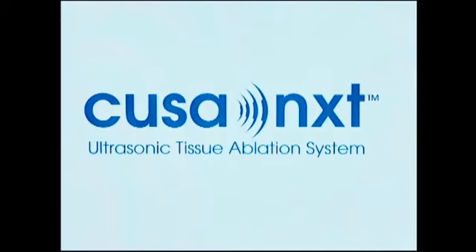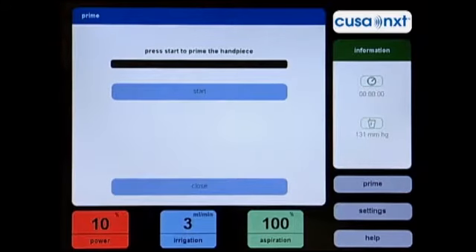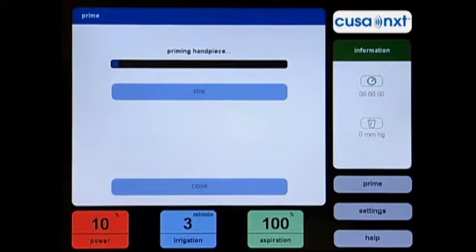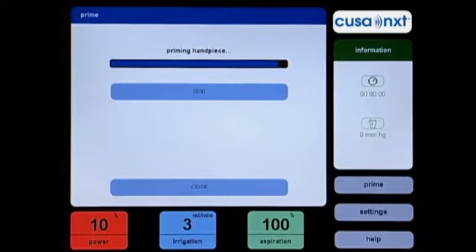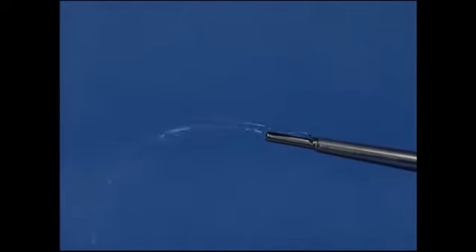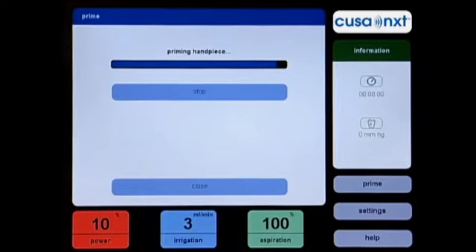After the system computer has successfully booted up, you will see the Prime screen. Press the Start button to automatically prime the handpiece with the irrigation fluid. The prime cycle will take approximately 60 seconds. Confirm the fluid has filled the flue around the tip. You may press Prime again if fluid has not yet reached the tip, and you may press Stop at any time to turn off the priming pump.